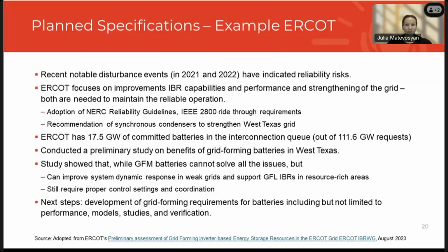If we're talking about planned specifications, recently there have been notable IBR disturbance events you must have heard about, specifically in the US, and NERC has released a number of reports. I think it's more than 10 now from 2016 up to now, where large amounts of inverter-based resources are tripping after a normally cleared fault, where they would be expected to ride through.